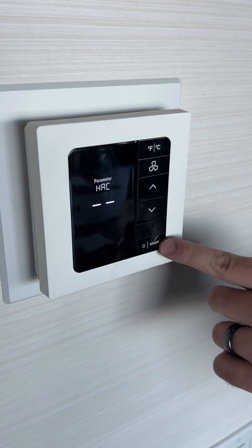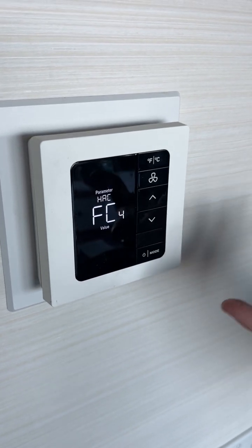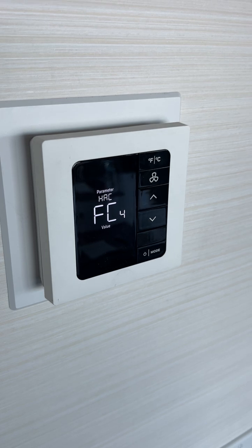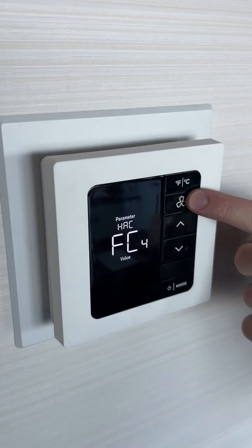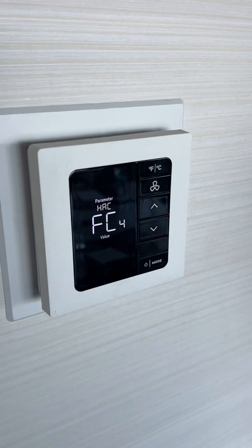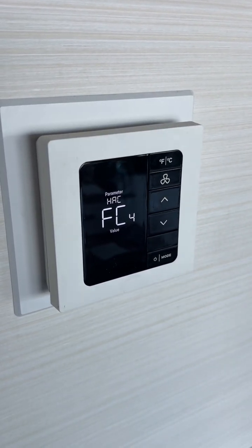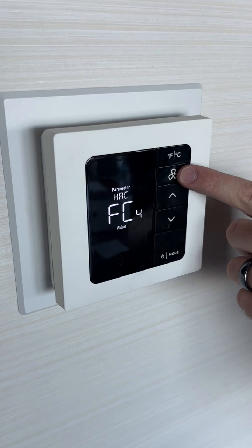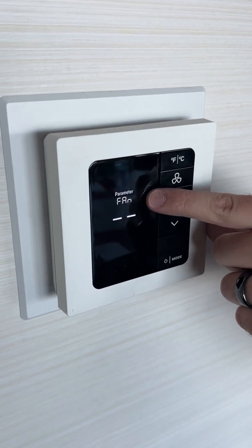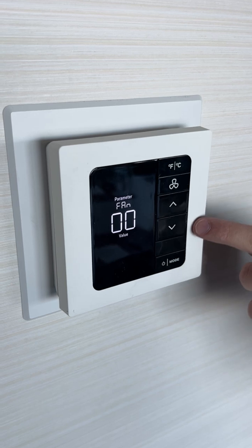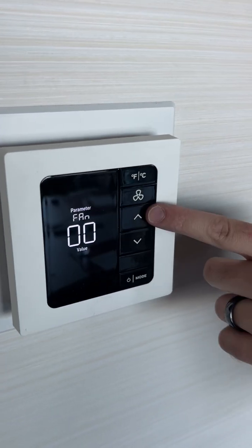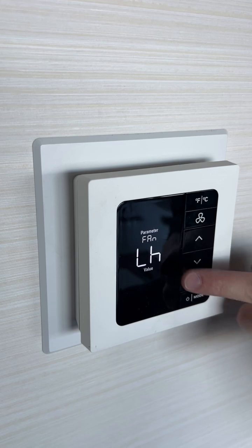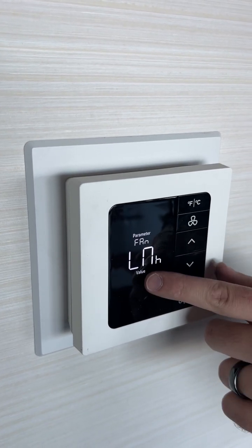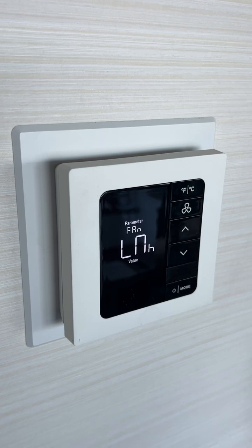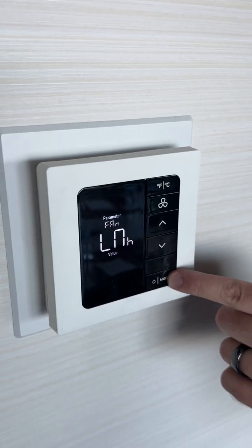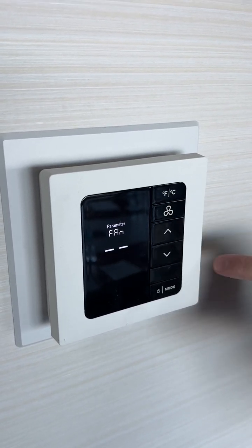We go to HAC, mode enter, up once to FC4, which stands for fan coil 4 pipe. In this case the thermostat's acting as a remote, so we're telling it when it should turn on - FC4, fan to save. Then we see fan populate, mode enter, and say it's got 3 fan speeds. Scroll up, we see LNH - low, medium, high, where N is supposed to be an M. So we set low LNH, then press fan to save.